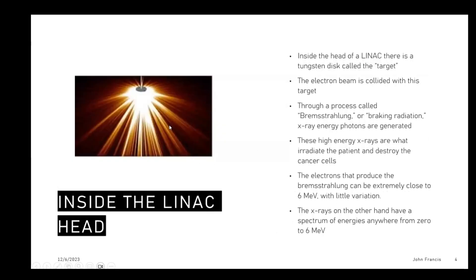Inside the LINAC head, there's a metal disc called the target. The electron beam collides with the target and creates X-ray photons. This process is called Bremsstrahlung, which is German for 'braking radiation.' Basically, as the target slows down the electrons, to account for that lost energy, it creates a photon or X-ray. As you can see in the picture, the photons are spread out all over the place.